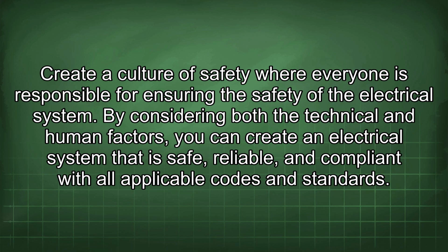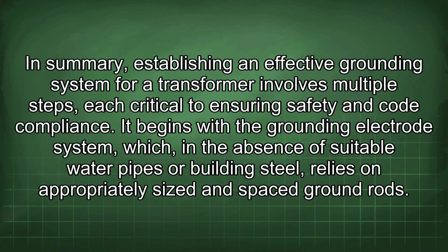By considering both the technical and human factors, you can create an electrical system that is safe, reliable, and compliant with all applicable codes and standards. In summary, establishing an effective grounding system for a transformer involves multiple steps, each critical to ensuring safety and code compliance. It begins with the grounding electrode system, which, in the absence of suitable water pipes or building steel, relies on appropriately sized and spaced ground rods.